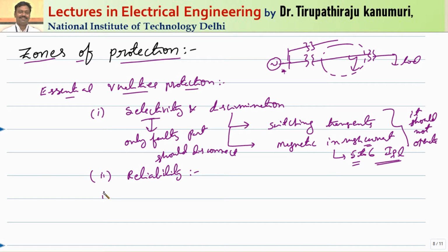These things we have already discussed in our previous class. I want my system to be very reliable. To have reliability, we generally go for backup protection along with the primary protection, so that even if some components of the protective system fail, the system still works. Because we have seen in the last class, the protective system contains, along with the circuit breaker, a CT and PT, that means current transformer and potential transformer, a relay, and a separate DC power supply. There is an actuating signal that will pass to the circuit breaker. So if any component doesn't work, then that system will not work. So always some backup will be required in order to increase the reliability. That we are going to see in detail soon.